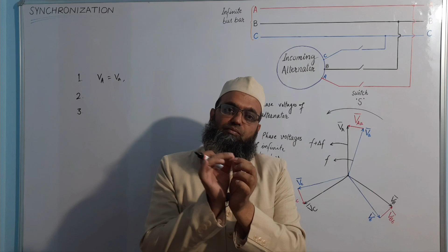Similarly, the moment when this VA coincides with this VA, the two potentials become equal. This VB coincides with this VB, and the two potentials, this point and this point, on either side of this switch will be equal. So there is no harm in closing the switch at that moment. Similarly for this also. But if phase sequence is not same, that is opposite to that of incoming alternator, then the moment when this VA will coincide with this VA, the other two sets of phasors VB and VC will be out of phase by 120 degrees.